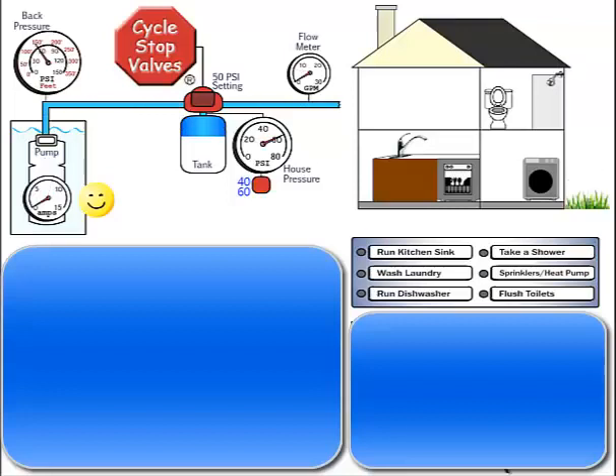Rarely is a single toilet flush the only water used at a given time. But even if you flush a toilet once, 50 different times per day, when no other water is being used anywhere, it won't hurt the pump. Those 50 cycles for individual toilet flushes would have been canceled out by the CSV having eliminated many repetitive cycles for longer-term uses like showers.